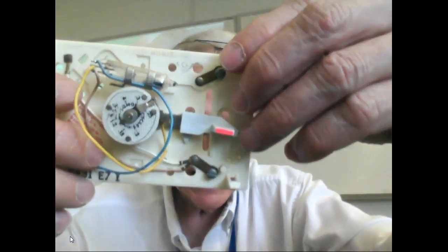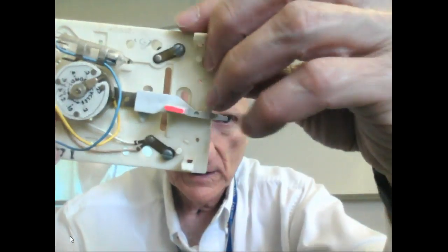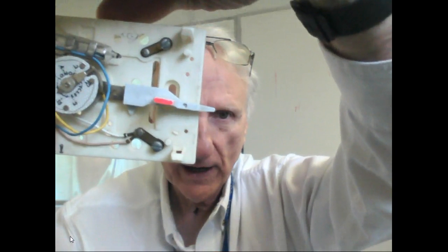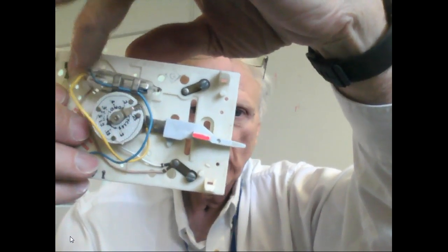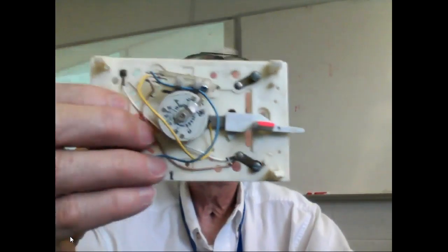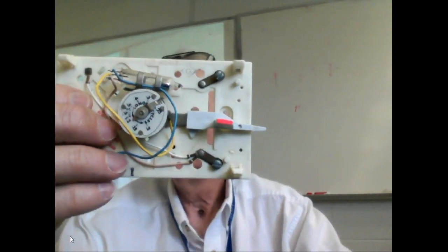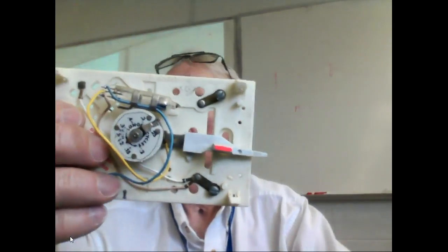There's a contact up here, and there's a contact back here. Depending on which way the spring ran, if it went this way, it would cover up the contacts on the back, or if it went this way, it would cover up the contacts on the front, which is pretty neat. You'll probably still run into these in houses that have been around a long time. Most thermostats now are digital, using an electronic sensor to sense the heat instead of a bimetallic strip.